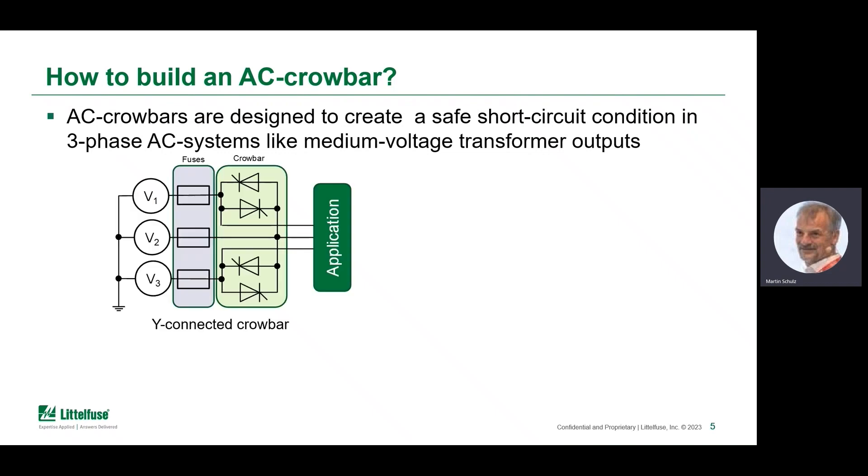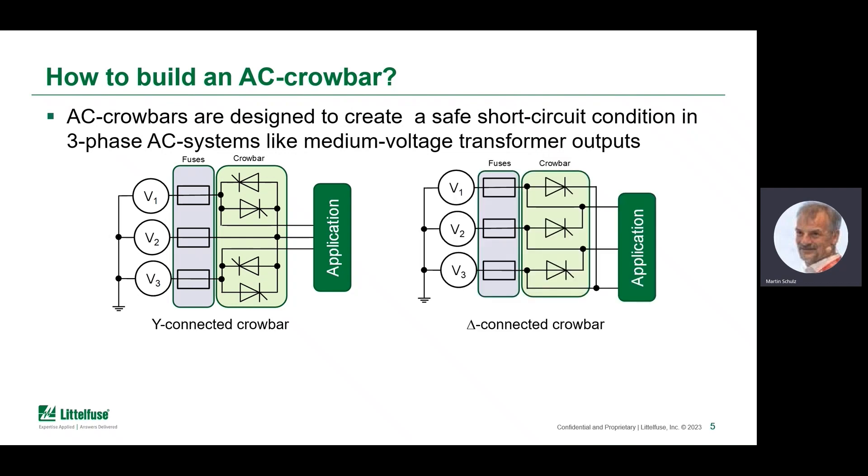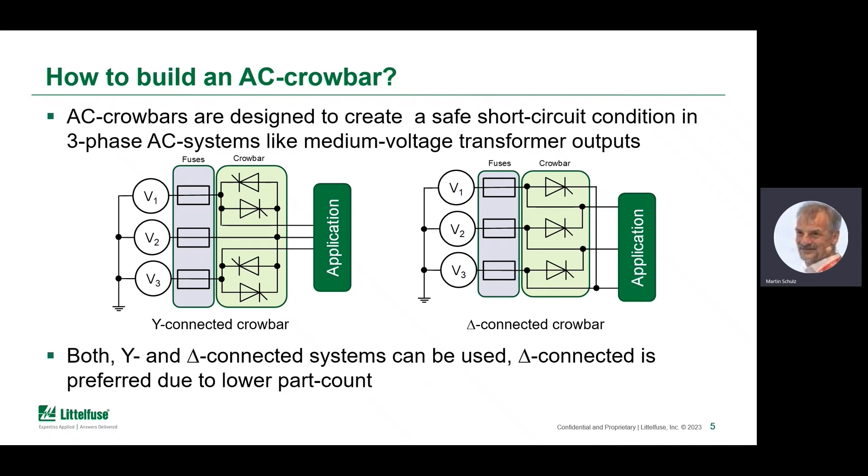A crowbar could be built using four thyristors in a Y-connected setup, which is sufficient to trigger short-circuit currents in both directions, leading to high currents that trigger the fuses. However, a delta-connected approach achieves the same using only three thyristors. Though both are considerably okay, the delta-connected one is preferred for economic reasons and the lower part count.